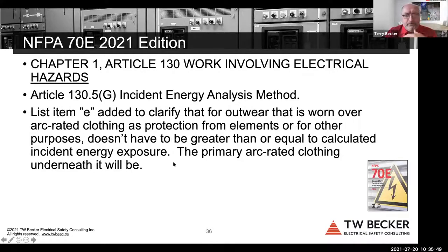again, it doesn't have to be great. Add a clarification for outerwear that's worn over it. So if you wear something over top, like it's cold outside and you wear an arc rated jacket over top of your arc rated clothing underneath, coveralls, that's fine. It just has to be arc rated, but it doesn't add to the actual arc rating. The actual arc rating would be the coveralls underneath, not the jacket that's arc rated worn over top.